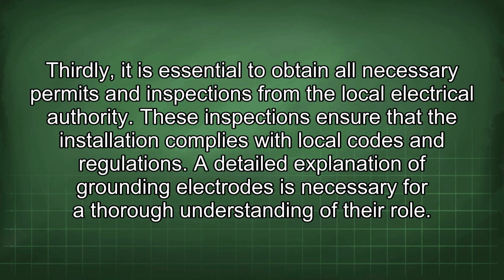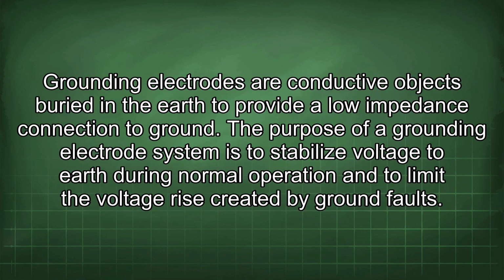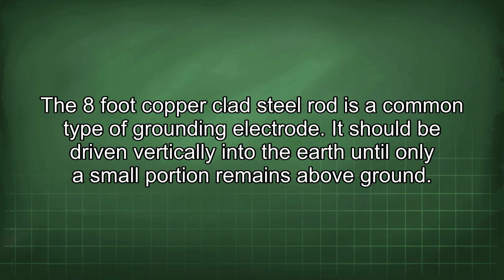A detailed explanation of grounding electrodes is necessary for a thorough understanding of their role. Grounding electrodes are conductive objects buried in the earth to provide a low impedance connection to ground. The purpose of a grounding electrode system is to stabilize voltage to earth during normal operation and to limit the voltage rise created by ground faults. The 8-foot copper-clad steel rod is a common type of grounding electrode. It should be driven vertically into the earth until only a small portion remains above ground.